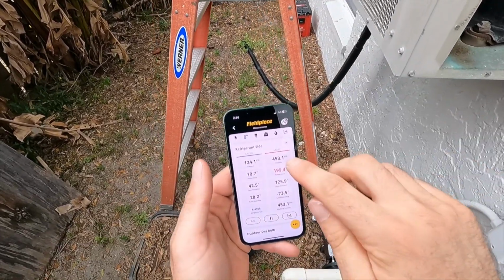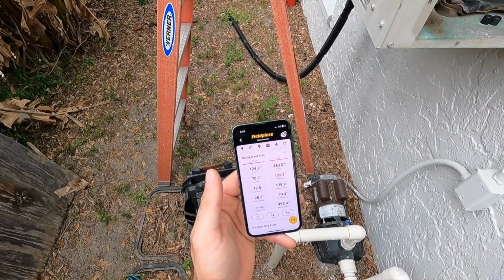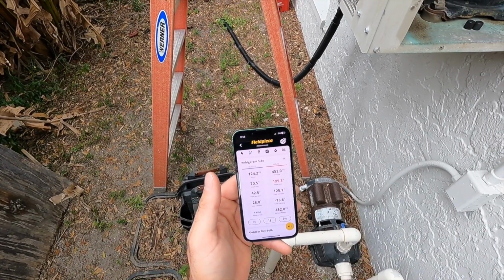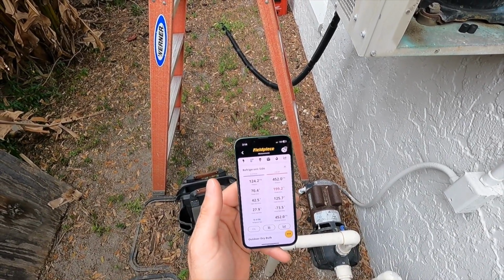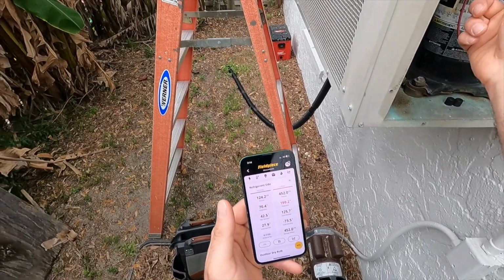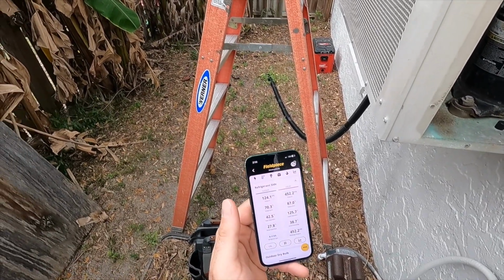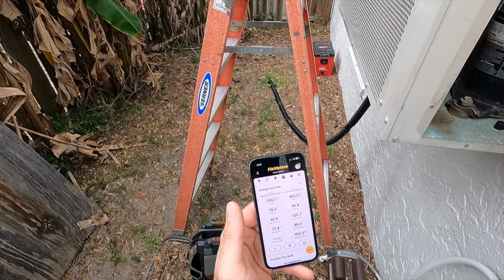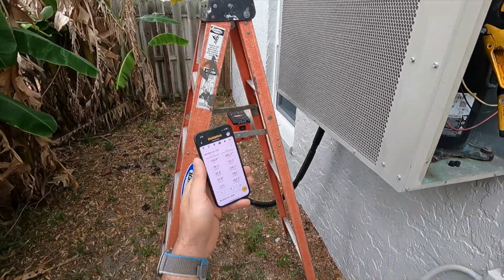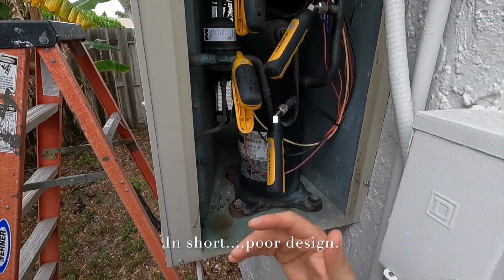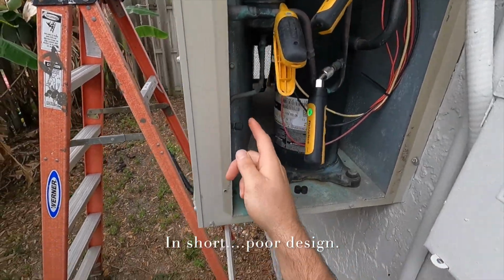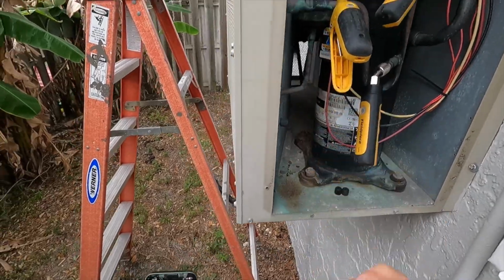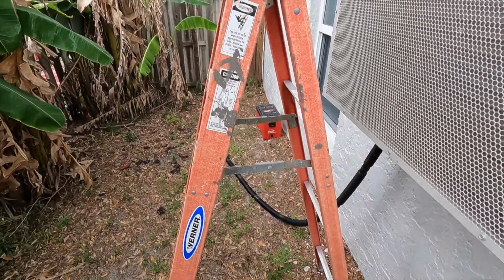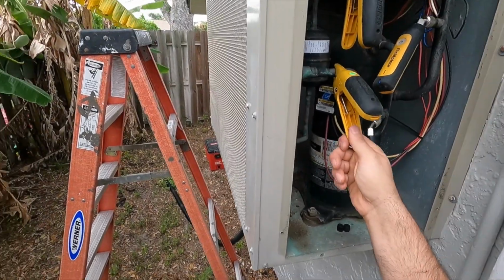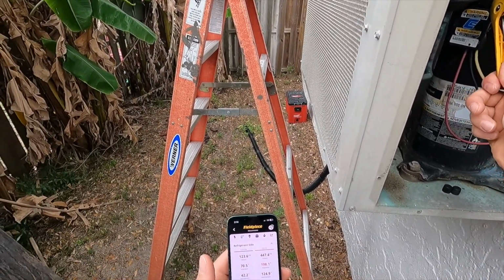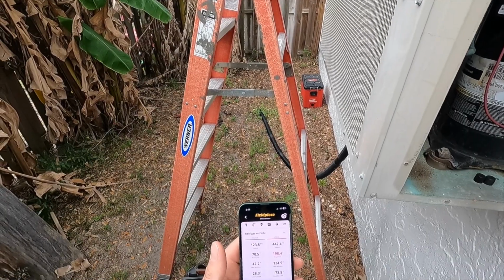that's okay. But you can see that head pressure there, 453, man, that is awfully high. But again, this unit, I've worked on it for a couple of years. It is known to run at a high head pressure just because of the design of the overall. You know, you got that much surface area for it. The air is being pulled in through the backside over this compressor on that side of the system as well, being pulled through and then blown out. So it's not a super efficient method for exchanging heat, but it's getting the job done.